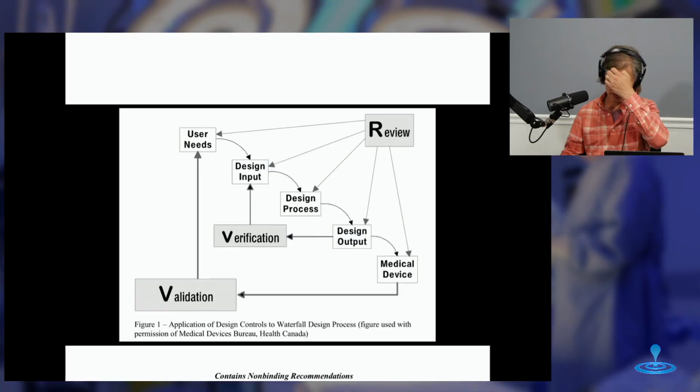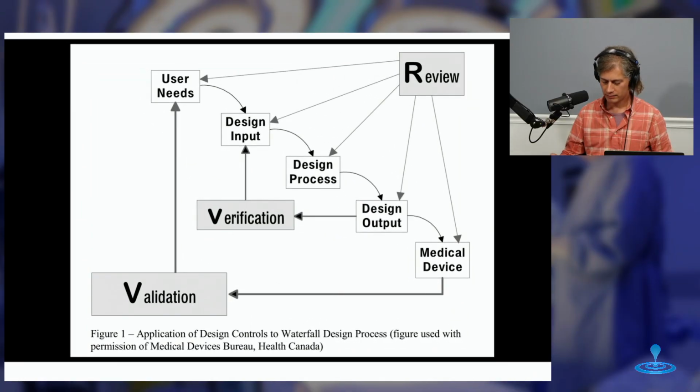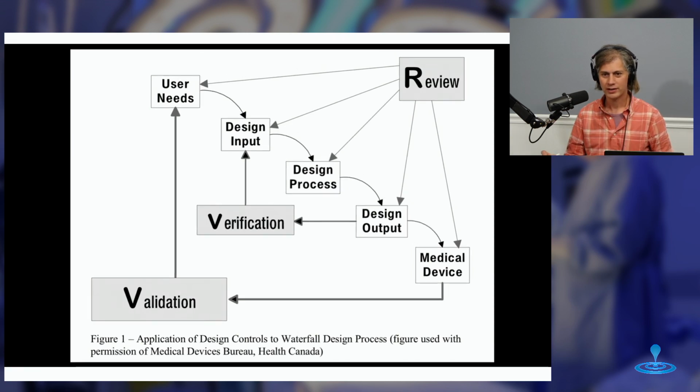Before we talk in detail about off-the-shelf software and how it's regulated for pre-market submissions with FDA, let's talk again just about how things get developed for FDA. This diagram, I left the figure 1 header on it because I don't think many people know this. I went back to the original source of this diagram, which is now proliferated all across the internet. Everybody uses this. I mean, we use this at Into Being. We'll show it to people. Where does it come from? It does come from an FDA document on design controls.